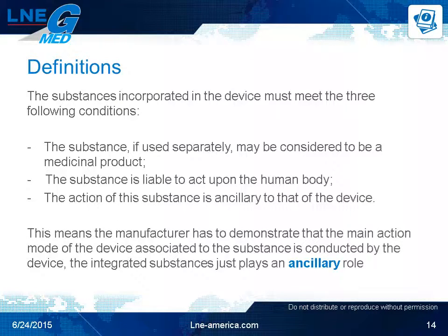The first condition that has to be met in order to consider the device a combination medical device: the substance, if used separately, may be considered to be a medicinal product. The second: the substance is liable to act upon the human body. The third: the action of this substance is ancillary to that of the device.